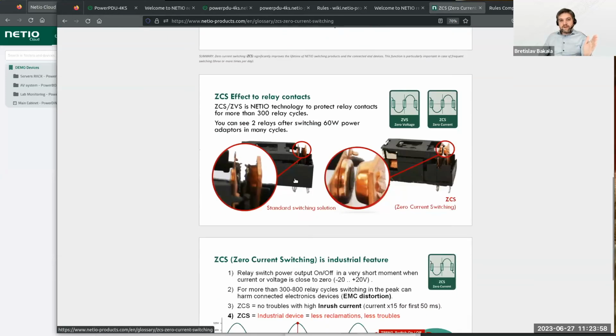This has a very big effect on preventing relay damage in the end. If you switch only at that point — and these are real photos I took myself, if you don't trust it you can come to Prague and I'll show you in our lab — it definitely prolongs the lifetime of the device. That's the first point. Secondly, it eliminates the effects of inrush current, because if you switch at zero potential, the inrush current peak is a little lower since it starts from zero and disappears within about 10 milliseconds. That's the first benefit.